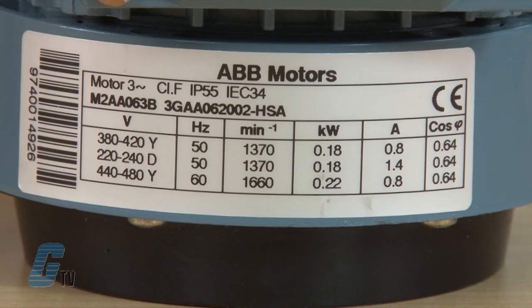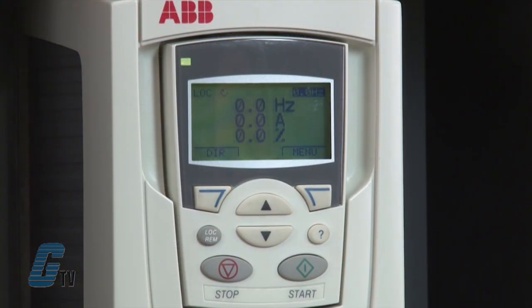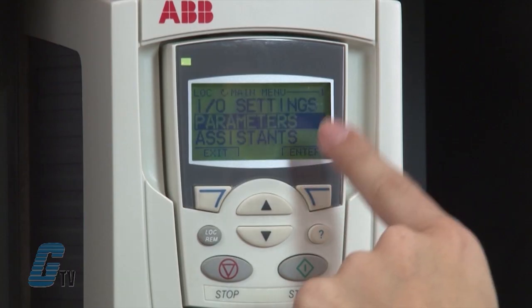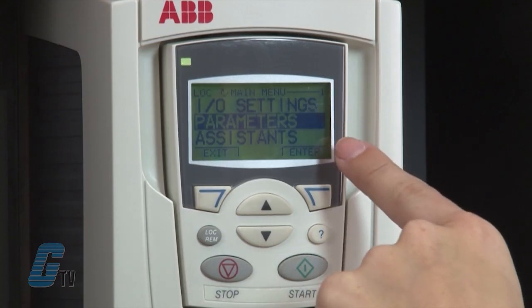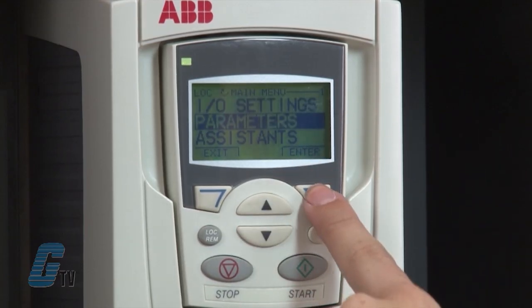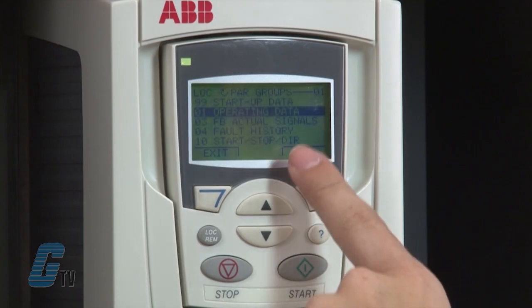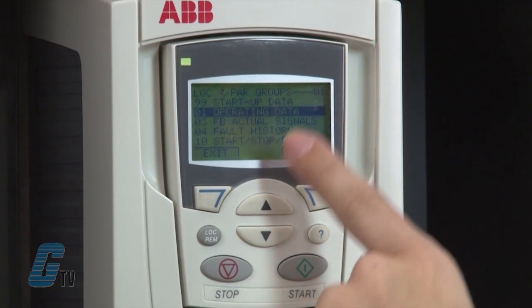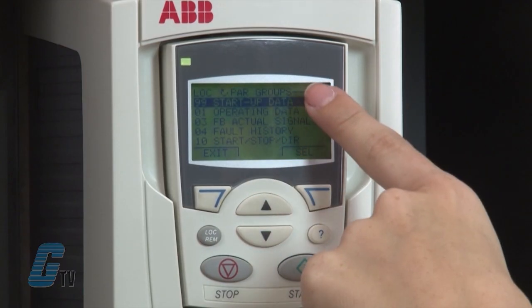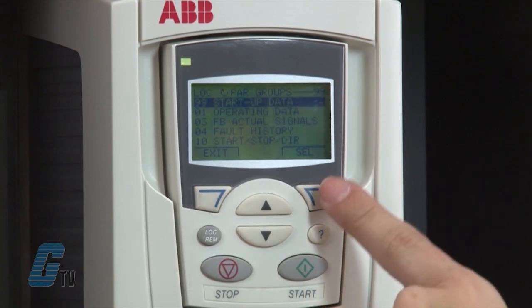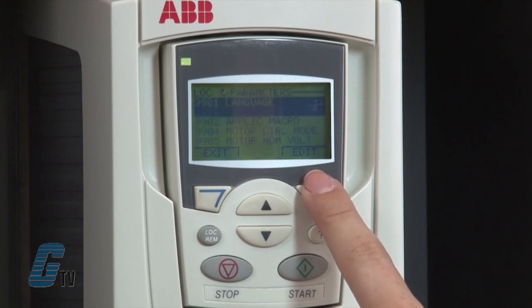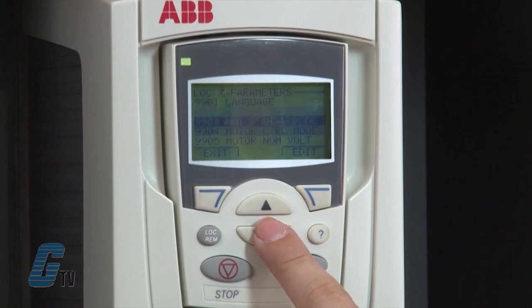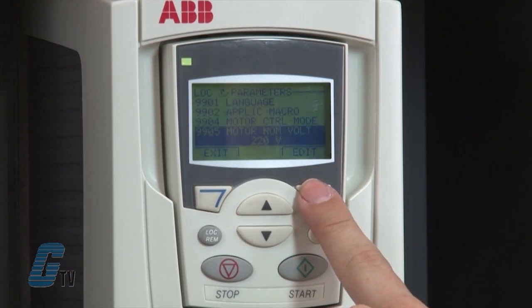Now that I have reviewed the control panel, I will begin to program the drive. First, I need to get the motor information from the nameplate that is typically attached to the motor. I will enter this motor information into the drive via the control panel. I'll push the menu button, which is currently the right soft key. The word 'Parameters' should be highlighted — if not, I'll use the up and down arrows to highlight it, then push the soft key for Enter. I'll push the up arrow once and group 99 startup data should be highlighted, then I'll push the Select button. I am now in the group 99 startup data parameter list. I'll arrow down to 99.05 motor nominal voltage and push the Edit button.